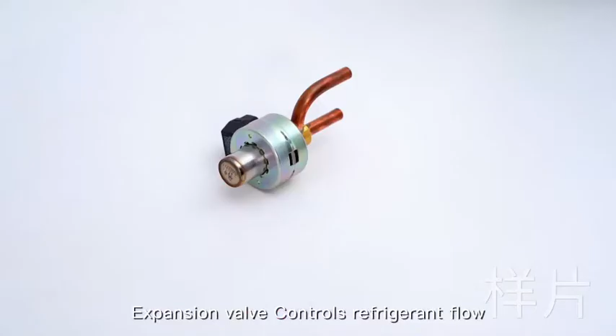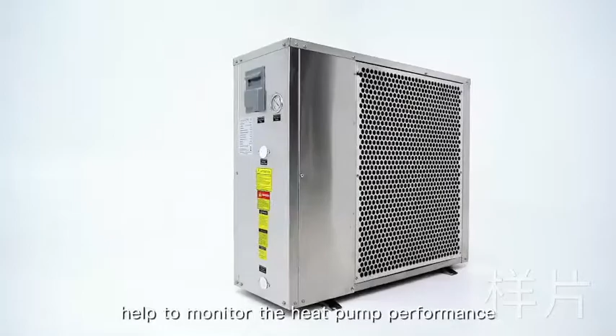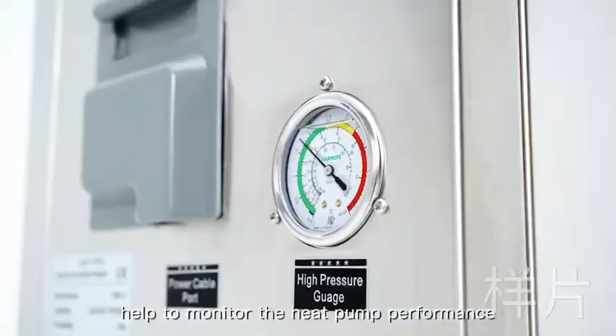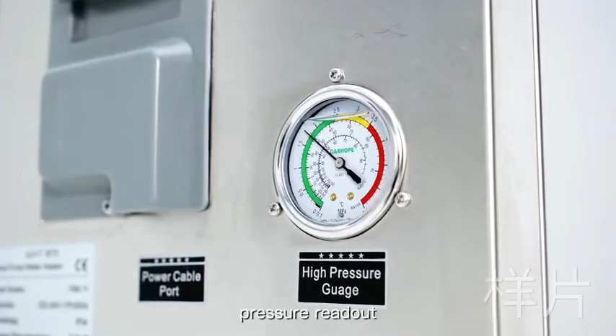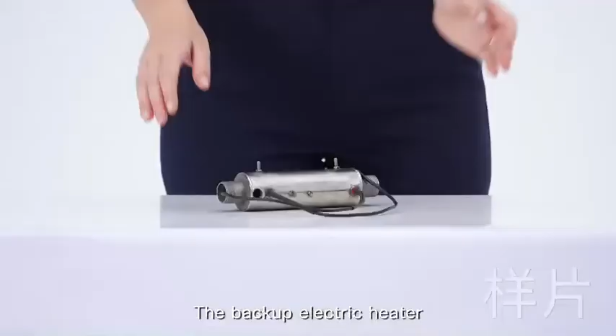The expansion valve controls refrigerant flow and reduces refrigerant pressure. The forced circulation pump maintains a constant, proper water flow rate, which will secure the heating performance and reduce after-sales problems. Also, there are some other secondary components that help to monitor the heat pump performance. The pressure gauge provides a water circuit pressure readout.